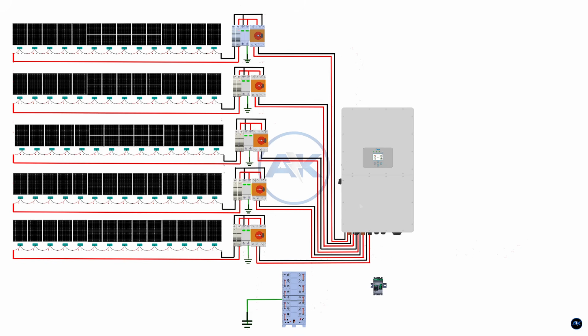With the battery breaker still off, connect the positive battery cable to the inverter's battery positive terminal. Then, connect the negative battery cable to the inverter's battery negative terminal. Tighten all terminals using a torque wrench according to the manufacturer's specifications. Loose connections can cause heat, voltage drop, and failure.